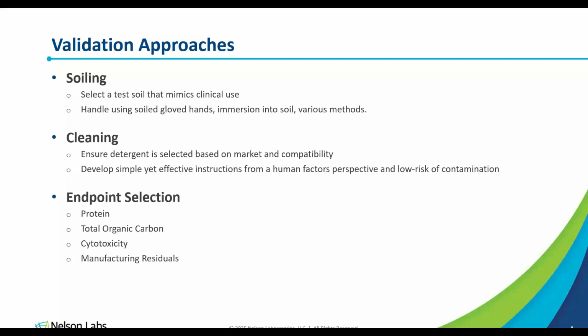In terms of cleaning, typically for a cleaning process, we want to select a detergent that is based on the market you intend to submit your device to. So in the US, neutral enzymatic detergents are preferred, whereas over in the EU, alkaline detergents are preferred. But that isn't the only thing you want to consider. You also want to consider compatibility of the detergent with your device.